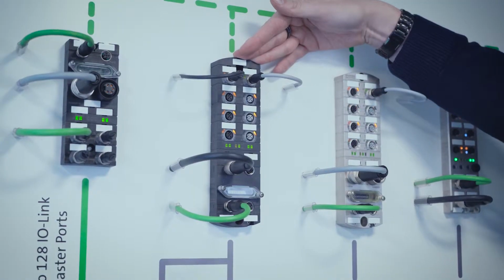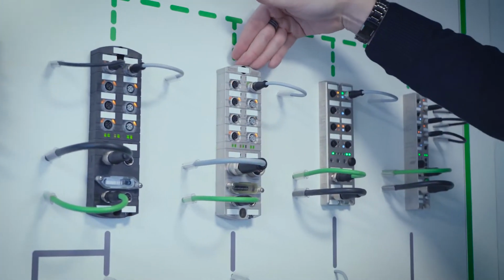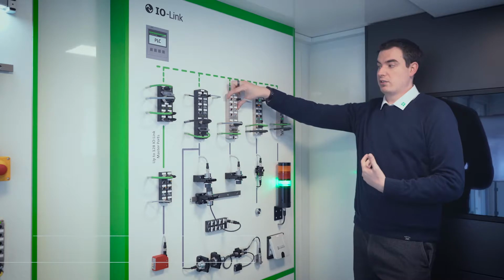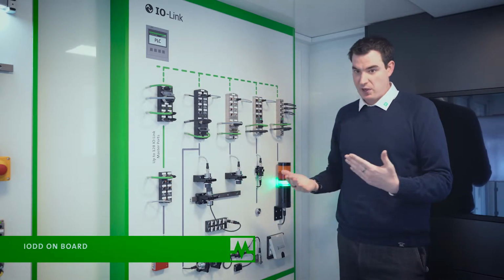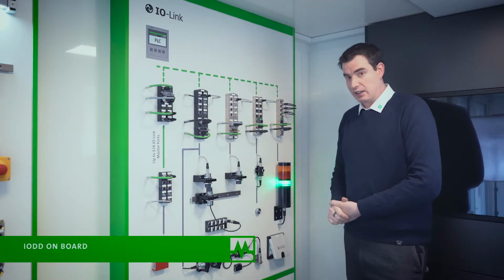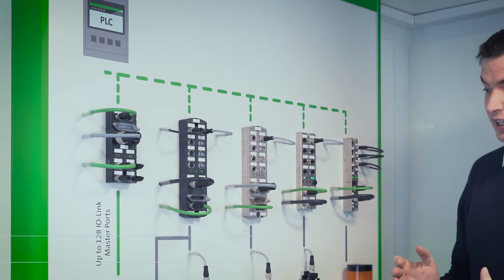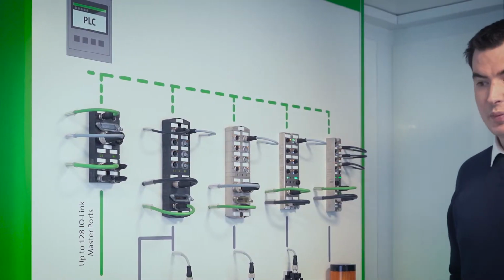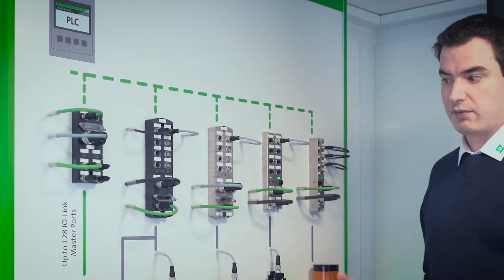In the case of our Impact and MVK, we also have the ability to do what's called IODD on board. This enables you to set the sensor up as part of the hardware for the PLC, and doing so then makes it a much easier, much simpler setup because there's only one point of configuration.